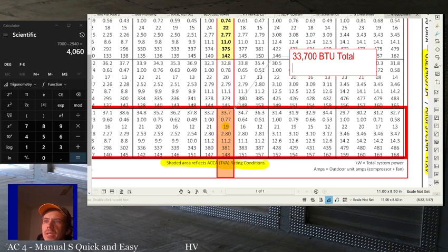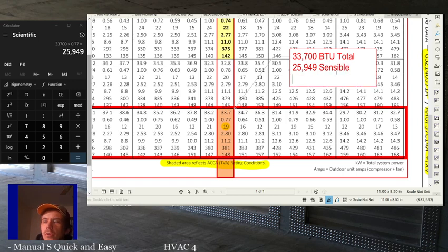All right, so that means 77% of that is sensible, right? That's what they're telling us here. So if we do 33,700 times 0.77, that means 25,949 is sensible. So if we subtract that from the total, we'll find out how much we got latent. So again, it was 33,700 total. Now we know that 25,949 of that was sensible. So we know that the latent load has to be, or the latent capacity rather, has to be 7,751.